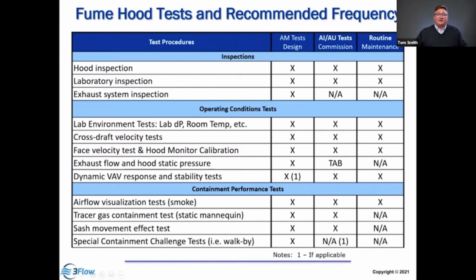And then on an ongoing basis, the routine maintenance tests are the inspections plus our flow measurements, velocity, and dynamic response. And then we only have to do a smoke test, right? If all these other conditions are operating properly, if the hood's operating the same as it did during as-installed, we'd expect it to give the same level of performance. But if it's beginning to modulate or any of these conditions have changed, then it may need to be recommissioned again to make sure that it's back to the correct operational state. So your routine tests are a simplified measurement, but they're not just face velocity. We have more tests to conduct, and I'll show you why as we move forward.